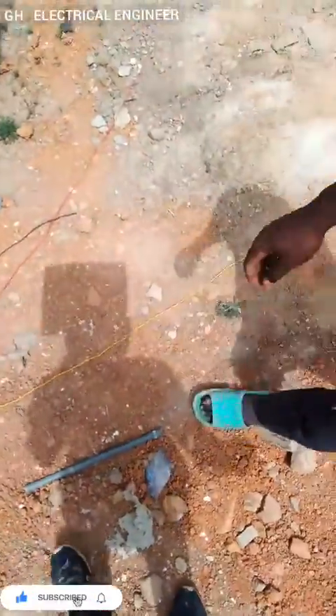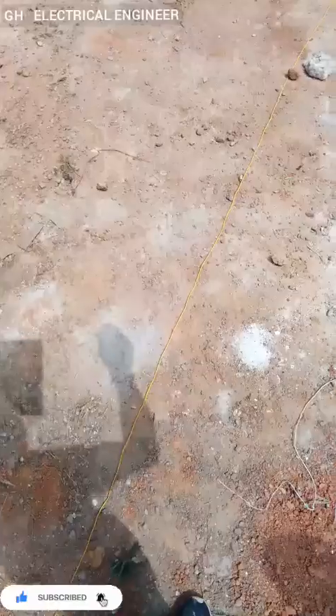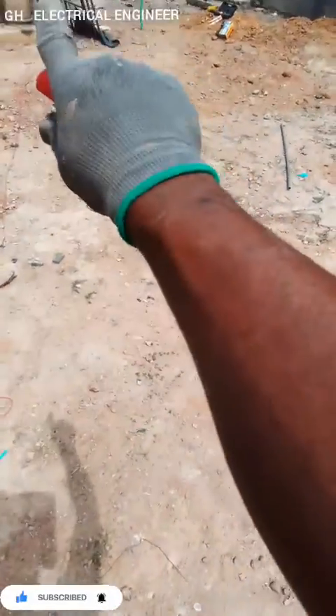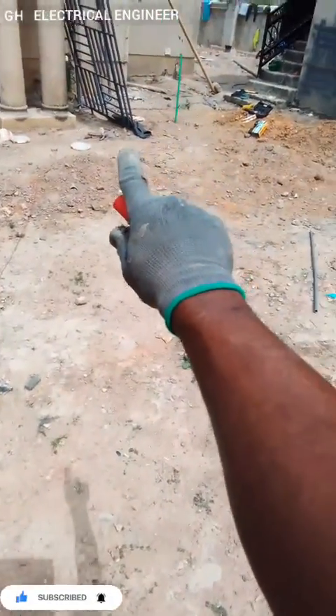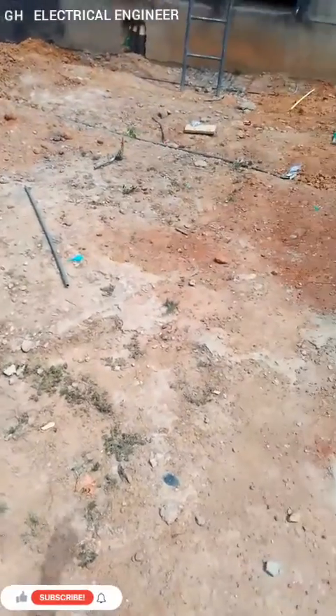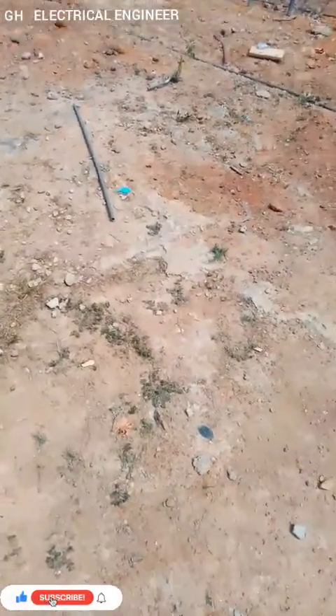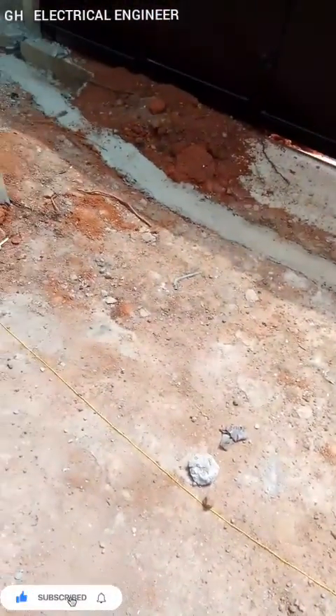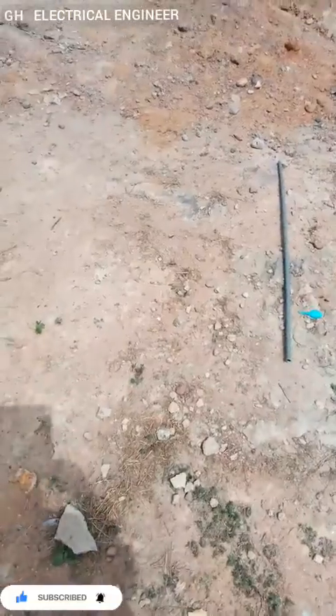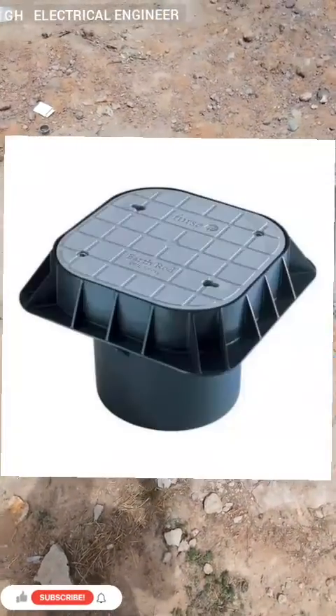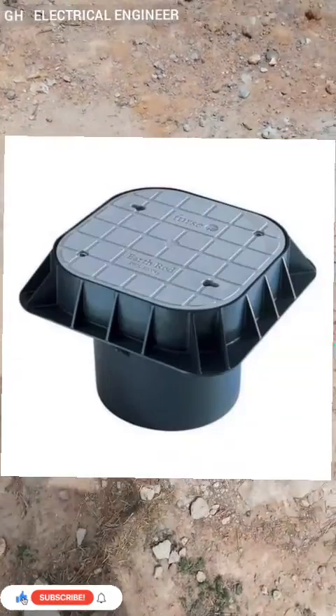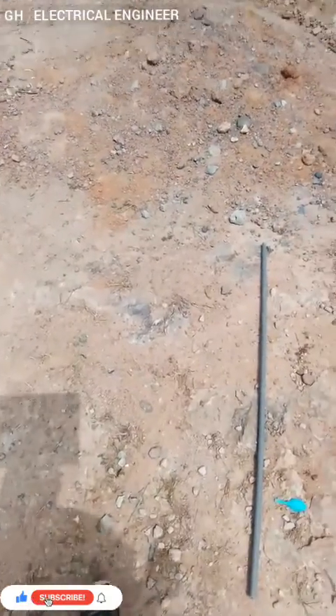It never comes easy. We spent almost 3 solid days just to get a low ohm reading for the client. Never easy. So what we'll do now is install a 60mm square or 25mm square copper conductor cable, drag it to the side, and put an earth chamber over it to make sure it's done right.